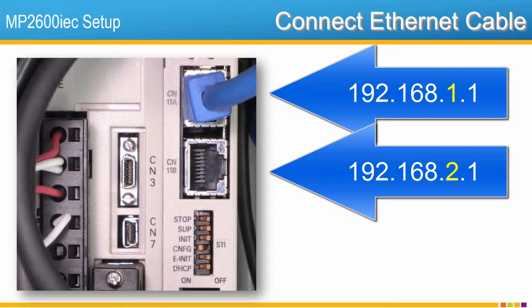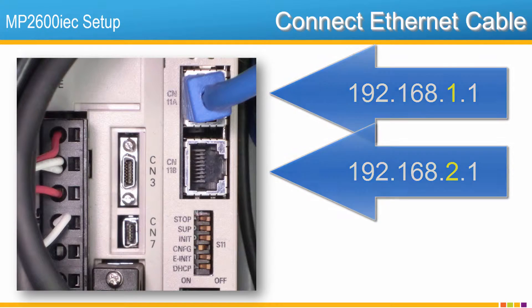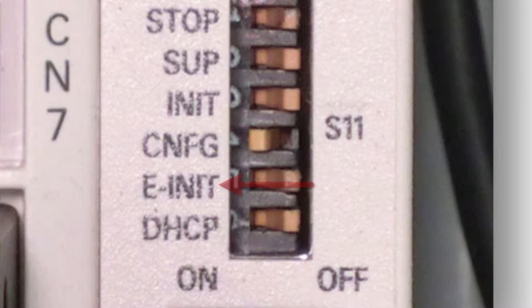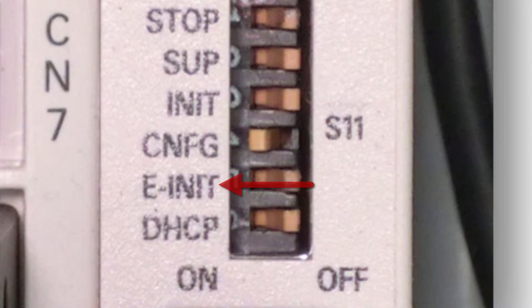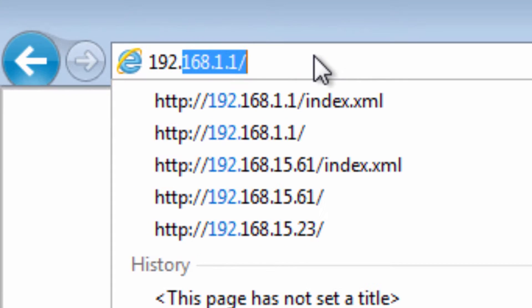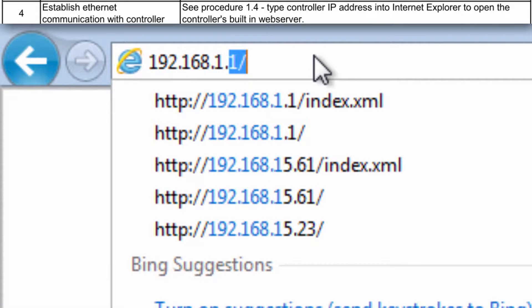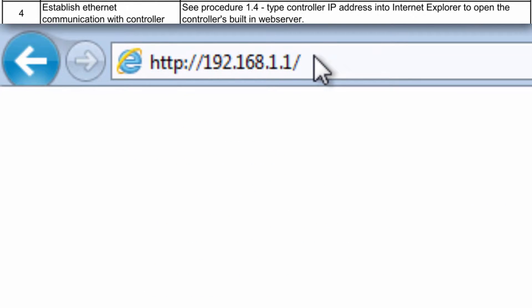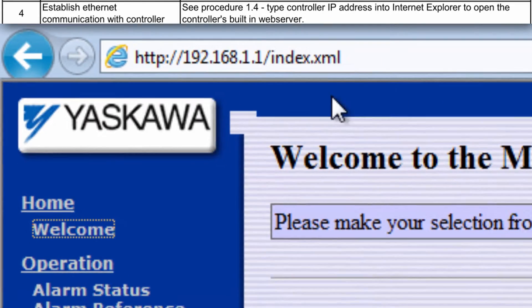If the controller is not new, you can still use this address, but you have to reboot the controller with the e-init switch on. Type the IP address of the controller into Internet Explorer, and the web server will appear.